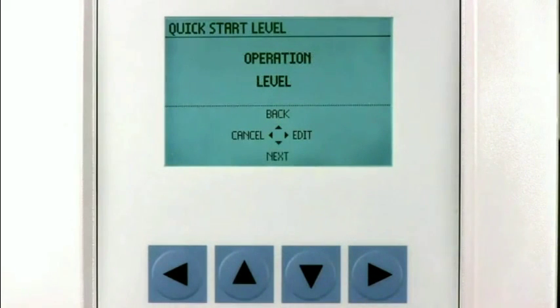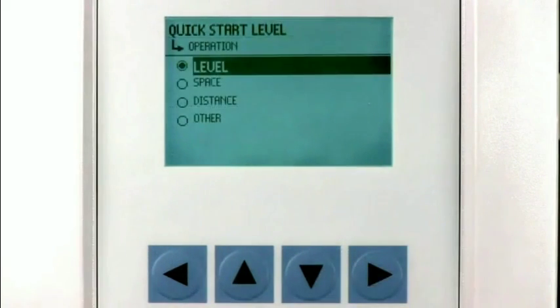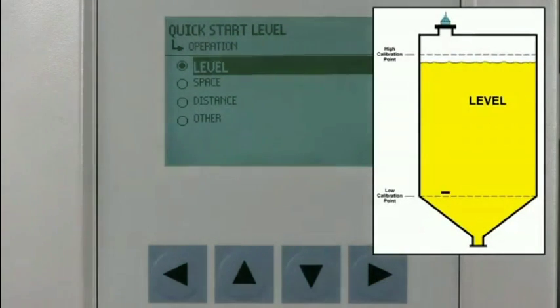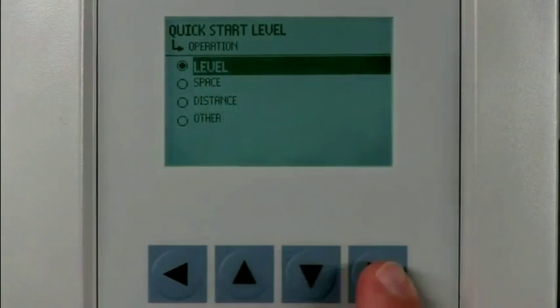The operation parameter defines the measurement mode used to calculate the displayed value and the corresponding milliamp output. There are three choices for this parameter: level, space, or distance. The level mode measures the height of the material in the vessel from the low calibration point to the high calibration point. The space mode measures the distance from the high calibration point to the material surface. The distance mode measures the distance from the transducer face to the material surface. In our application, we will select the level mode.